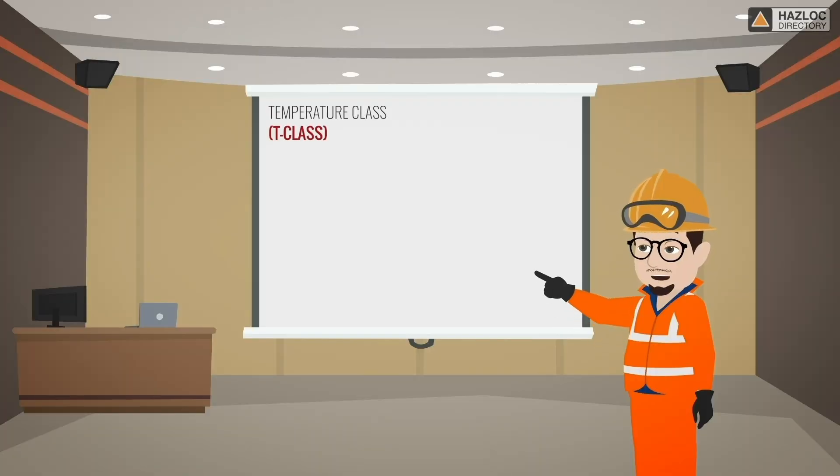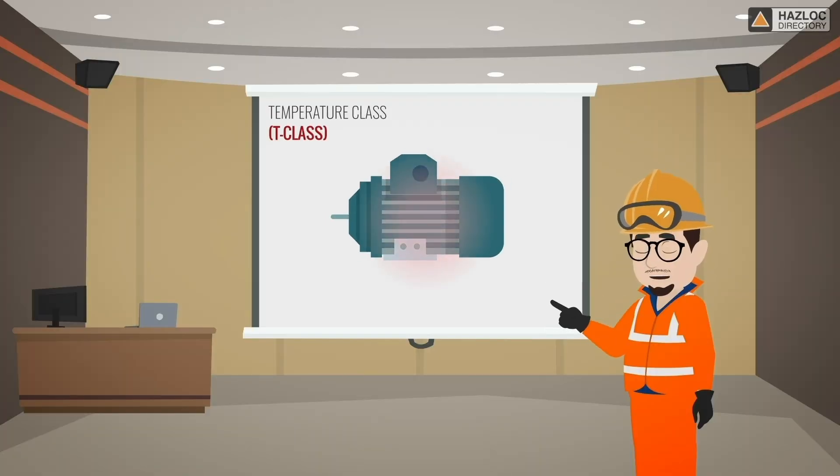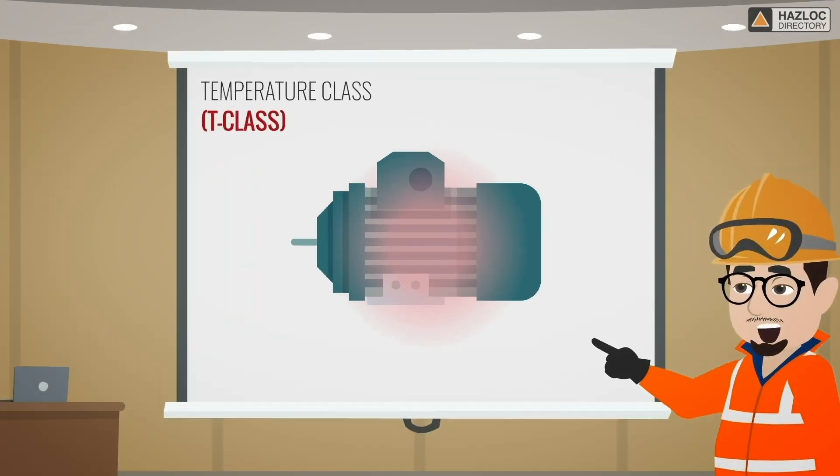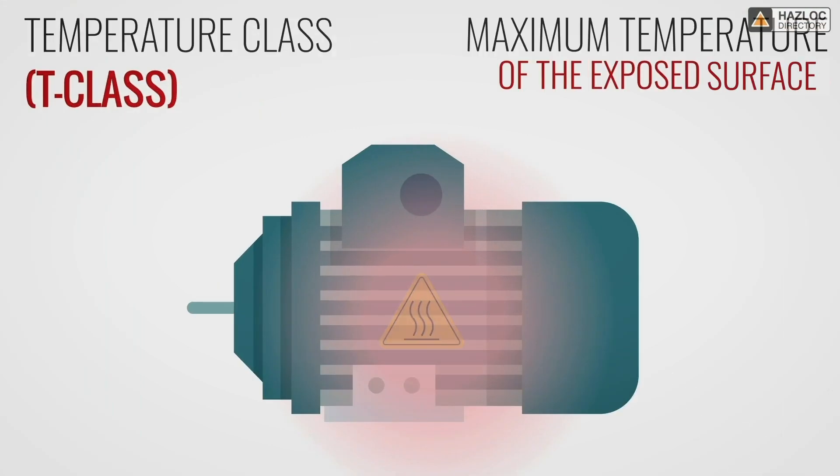Temperature class, known as T-class, is one of the characteristics used to classify an electrical device so it may be safely installed in a hazardous location. It is the maximum temperature of the exposed surface of the electrical apparatus based on the ambient temperature range allocated for that device.